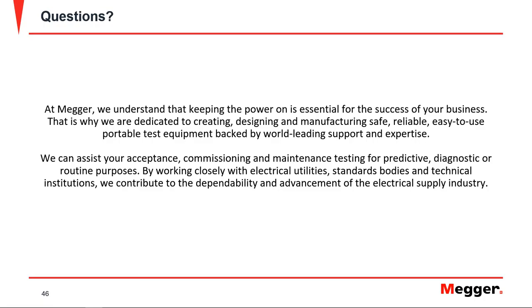Also, we have fuse manufacturers that do design testing of the fuses with this type of instrument. So while you are within the limits of the unit, you can use it for fuse testing as well. And there are some reclosers that are called TripSavers. Those are also possible to test with this instrument.